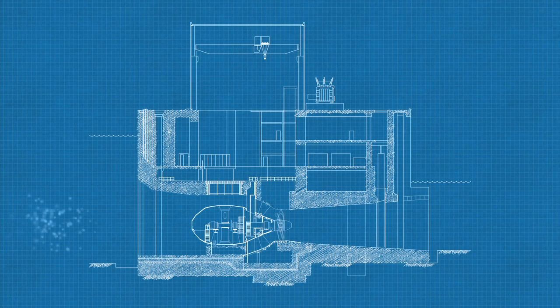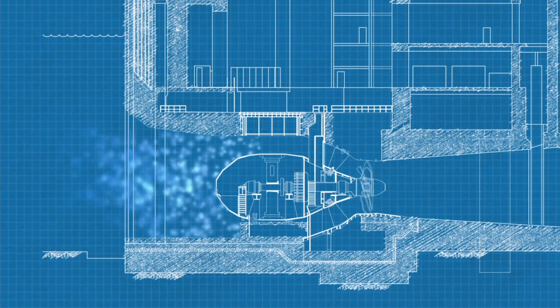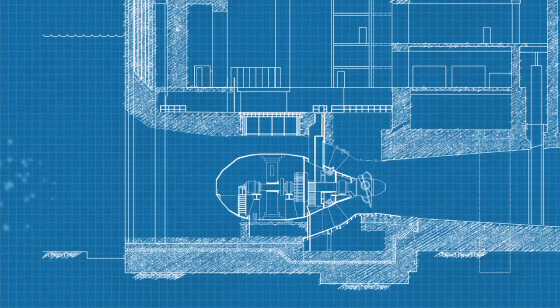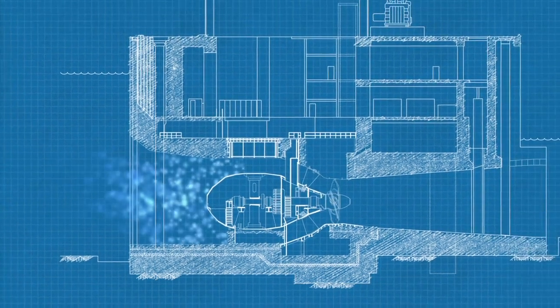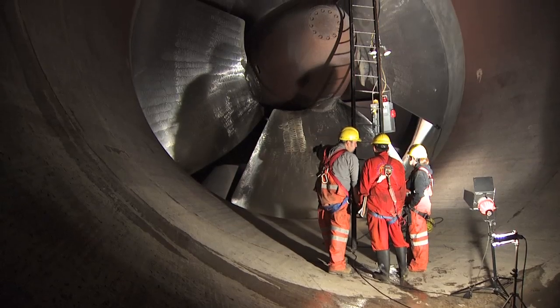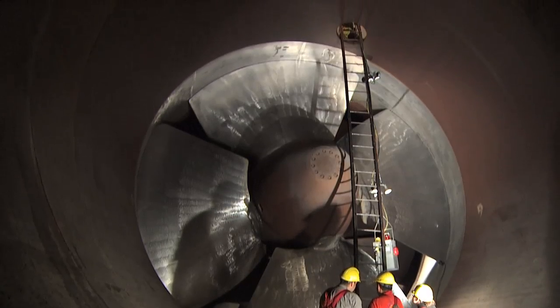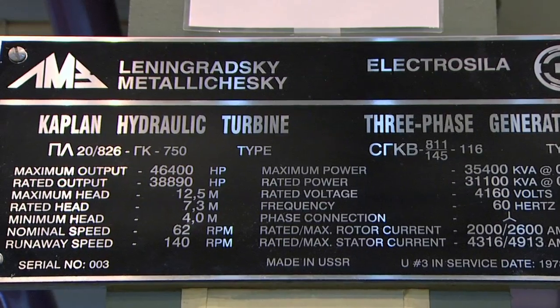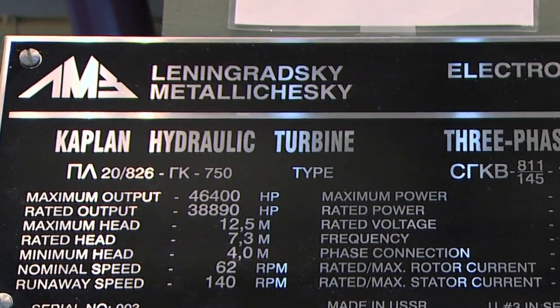But at Jenpeg, the turbine generators are positioned horizontally in the water flow. They're called bulb turbines, and they look like a miniature submarine. Designed and built in the Soviet Union, the water flows all around the turbine generator unit before exiting out the station's draft tubes. When these units were installed, it was the first time bulb turbines had been used in North America, and it is still one of the few places outside of Russia and Eastern Europe that features Soviet technology.